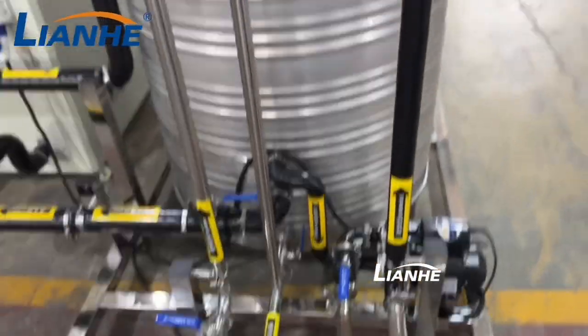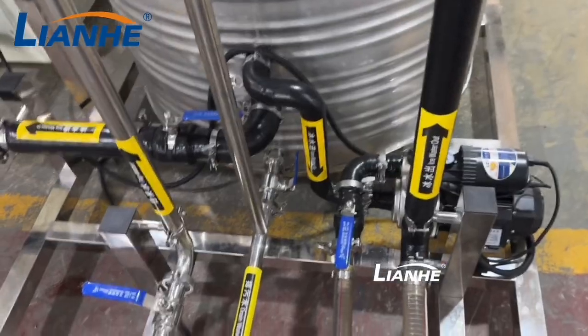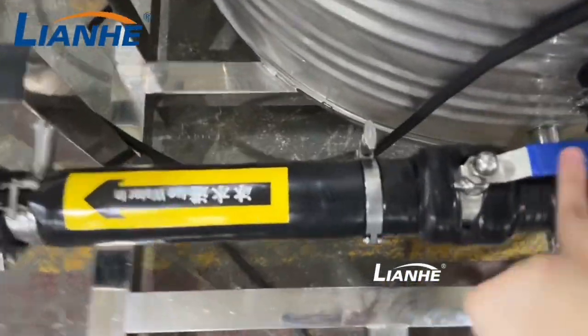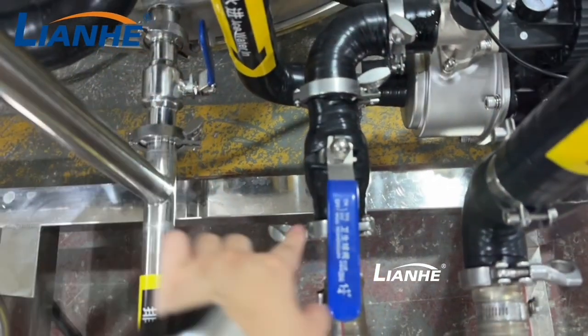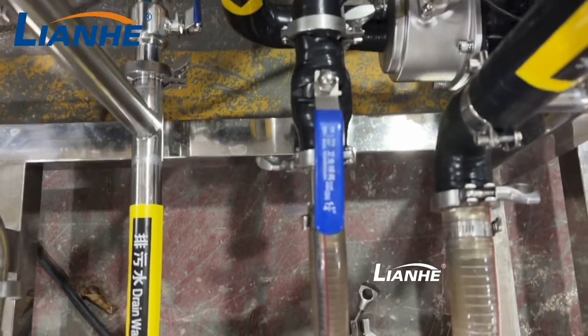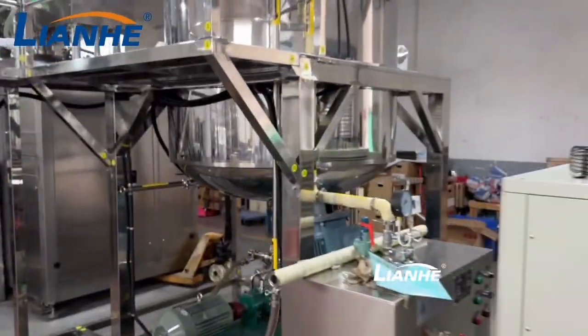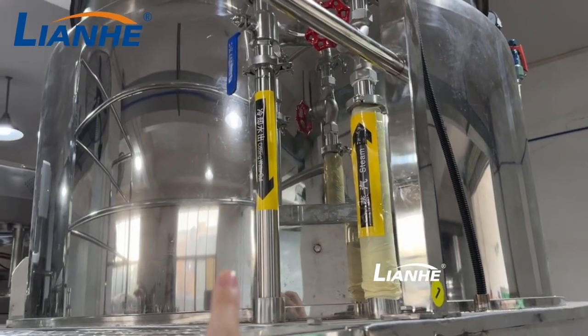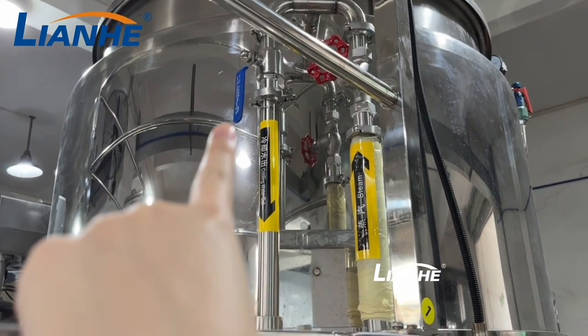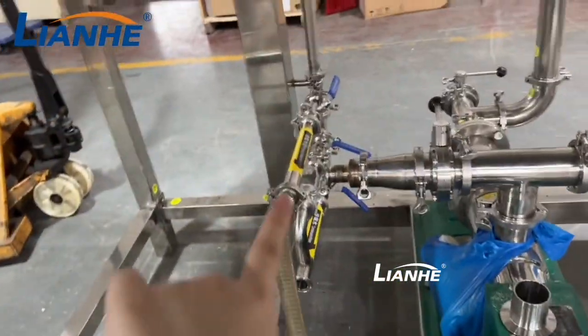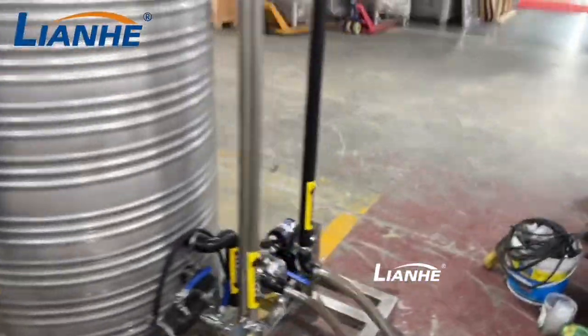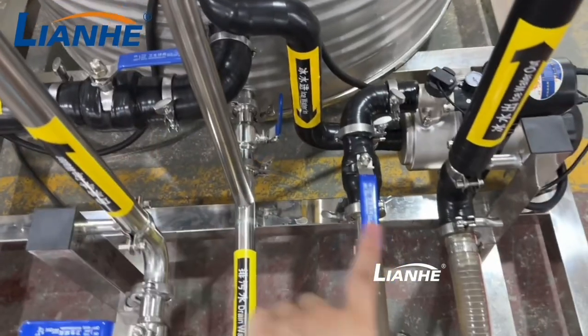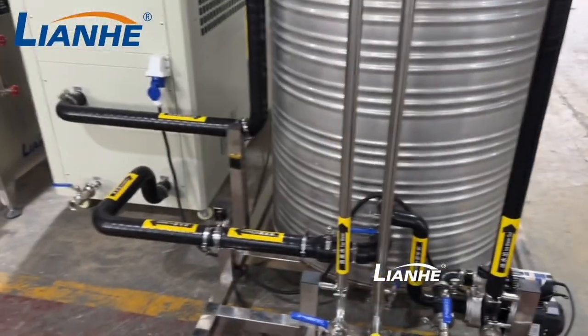Okay. And when the water is in these 2 tanks and you want to use the cooling function, you should make sure this valve is turned on all the time. And then you should turn on this valve too, to let the ice water come out from the tank into the jacket. Open this valve. And then when you want to use these functions, the first step is to turn on the cooling water out pipe valve. This valve should open firstly, and then open this valve secondly, and then turn on these valves. So you can use the cooling function.